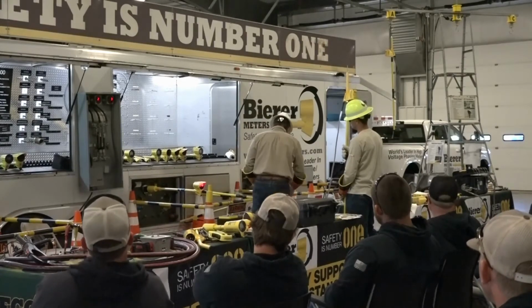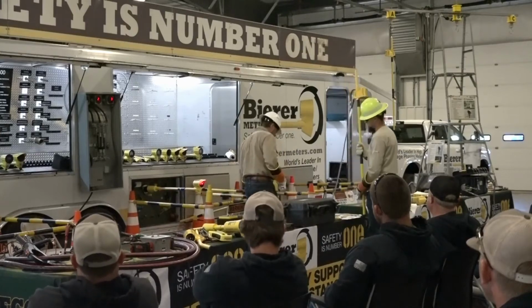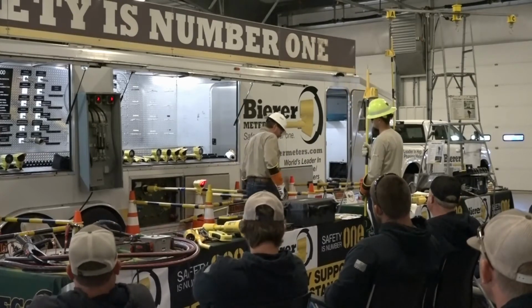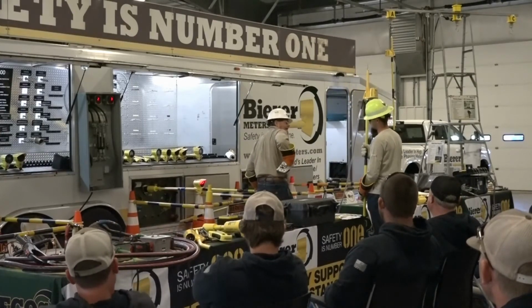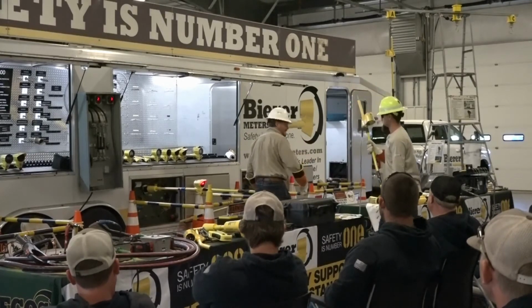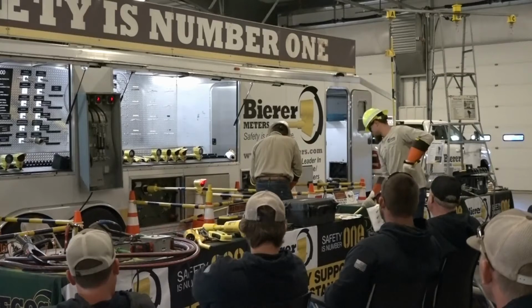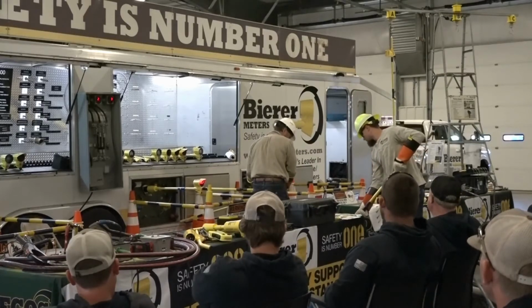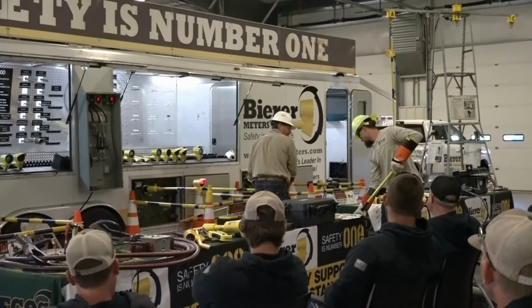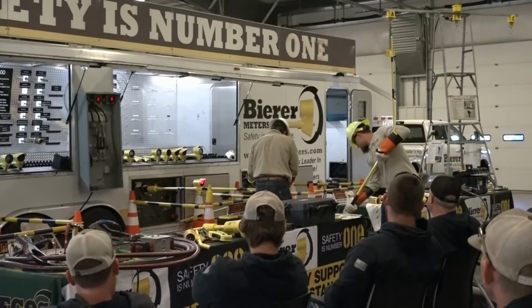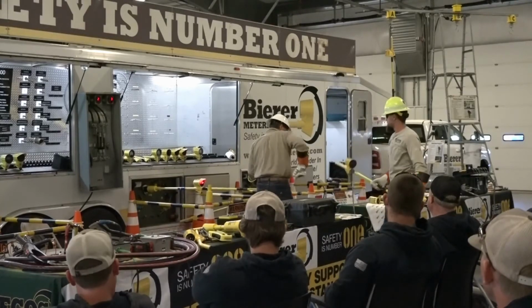All right, so what we're going to do is I'm going to get back on my stick. And Dylan, if you could read my foot, and then my back, and then the inside glove with the probe. Go ahead and make contact with my boot, and see what you get as far as your voltage. Right on that boot, 157. Is it? Yeah, that's pretty good, pretty high. All right, go to my back.